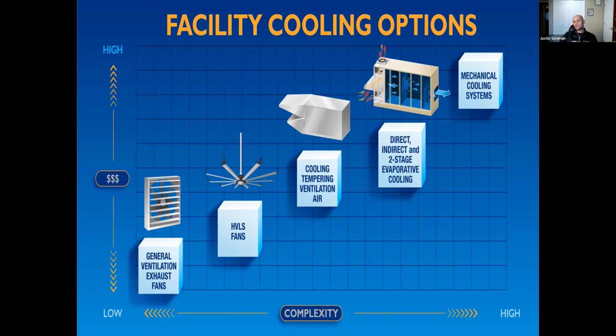So we started looking at other options that our customers consider, because in a manufacturing environment we are exhausting and throwing away most, if not all, of the air we've conditioned every single time we make a pass on that piece of equipment. When you start looking at direct and indirect evaporative cooling equipment, it's one step below mechanical cooling systems in price. It's roughly the same first cost, but the real savings kicks in on the energy usage. We were able to use less than 1/5 the energy using evaporative cooling technology compared to a DX cooling system. That doesn't necessarily mean, especially in our case, that evaporative cooling technology is going to add a bunch of complexity to the building.